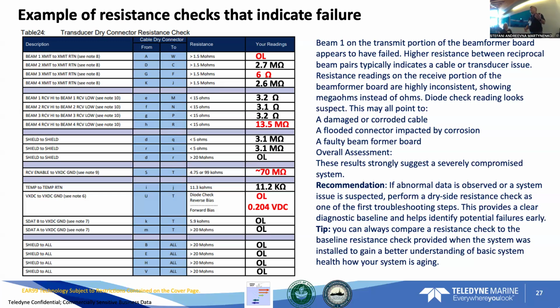And I think this is really beneficial and will really help you: whenever we do an install, we will provide you these checks. So you will have like a golden standard of how your system was when it was installed. And over the years and time, you can actually do this cable resistance check and it will help you see how your system's aging and possibly give you some indication of what's going on with it. If something's starting to fail, you have a beam starting to go, and you can probably see it slowly degrade over time, which gives you a heads up on what you need to do to correct your system.